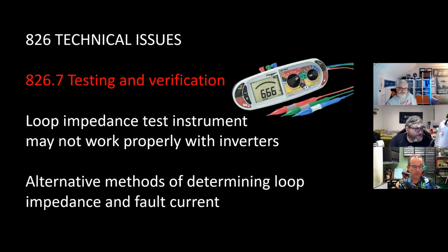So the alternative method is calculation. Is that what they're saying? Pretty much. It didn't actually state which it was, but it's going to come down to calculation and things like specification of the transformer and all that kind of stuff. Again, it depends on the inverter manufacturers, whether they want you doing it. I've grown up working with UPSs and inverters, and I've always done a test on the mains with it in bypass and a test through the inverter, and you normally got between 3/4 of an ohm added onto it, but I still wanted to check the performance and the safety of the circuit, as I would do. So I had 2 ZS values.